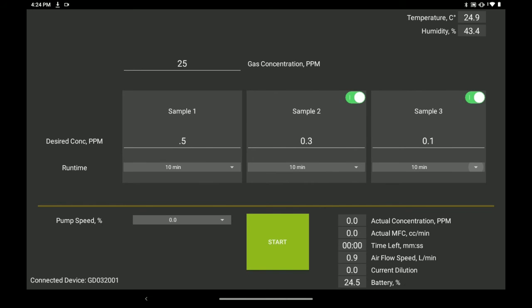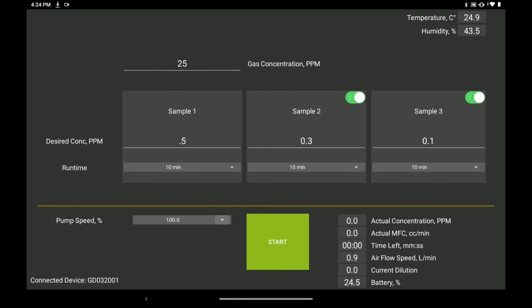Now what you're going to want to do is adjust your airflow speed. In our case, if you're using the pump, you just hit 100% and make sure that the flow rate is higher than the flow rate of your device. Once you're happy with your airflow speed, you then want to connect your canister and your analyzer to the unit. And then once that's done, you can go ahead and press start.